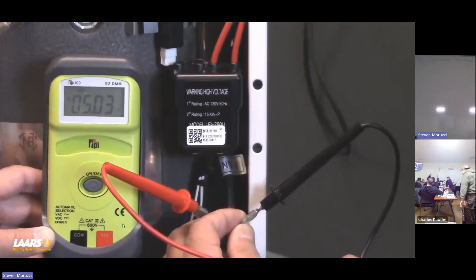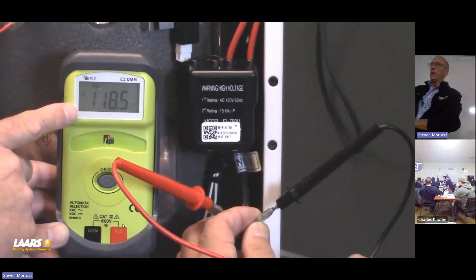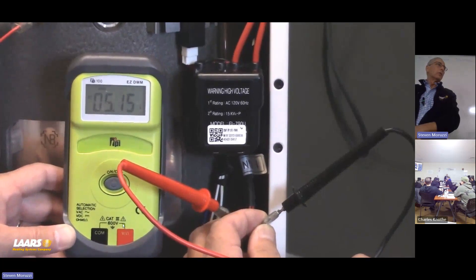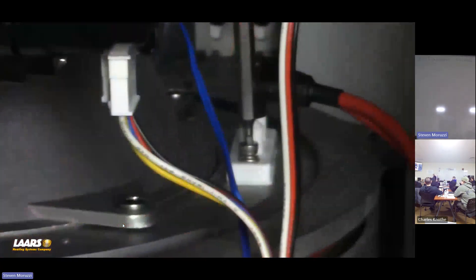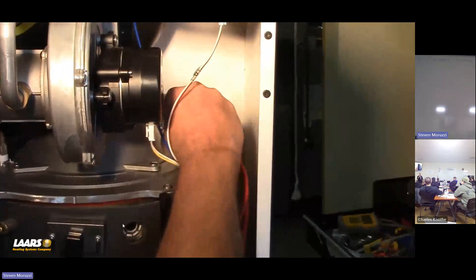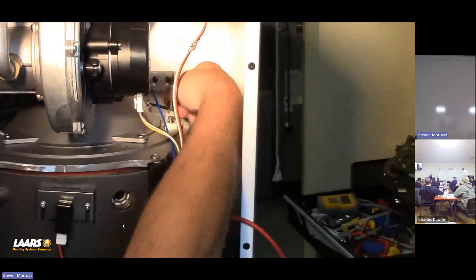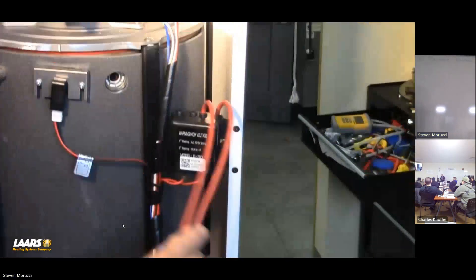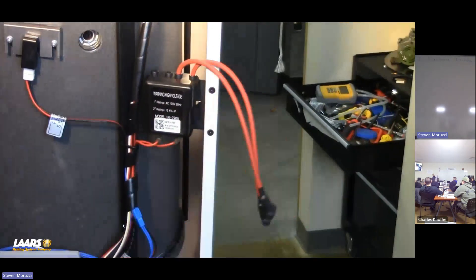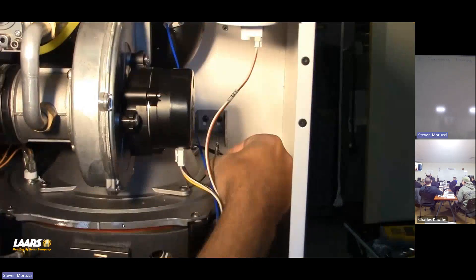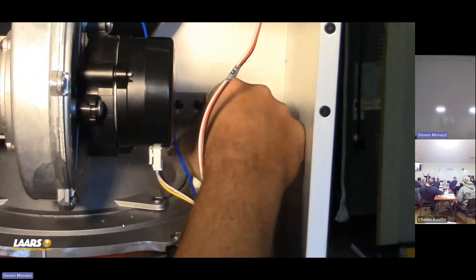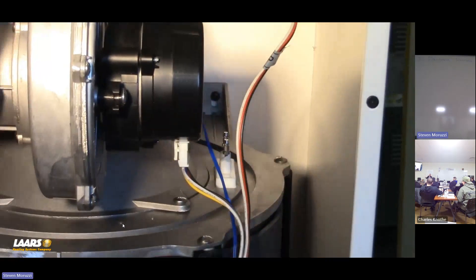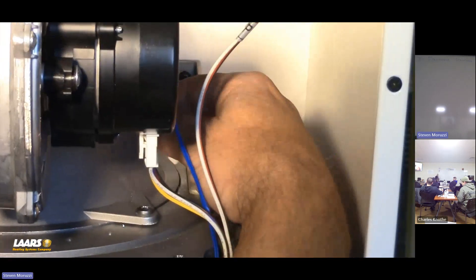Now it's going to purge again, make sure we get rid of any residual gas. We're going to re-energize there again. Here we're showing 118 volts. Short little intervals. We don't have a pilot on these. Pilots typically can give you 8 to 10 seconds depending on the commercial products. We have 10 tries for ignition, which would be error code 11, 8 on error code 10, which means we actually lit but flamed out. This order should have been flipped around. Checking my spark ignition should have been after error code 11, because error code 10 was about air and fuel.